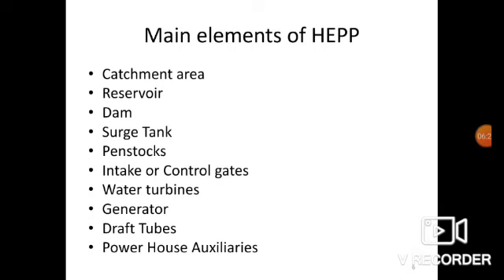Next is the draft tube — an airtight pipe of suitable diameter attached to the runner outlet, conducting water down from the wheel and discharging it under the surface of water in the tail race. Powerhouse auxiliaries: the hydroelectric power plant requires the same basic auxiliaries as any other power plant, such as governor system, exciters, cranes, control panels, and more. Power supply for auxiliaries, cranes, and lighting is usually arranged from a small independent hydraulic turbine and generator.